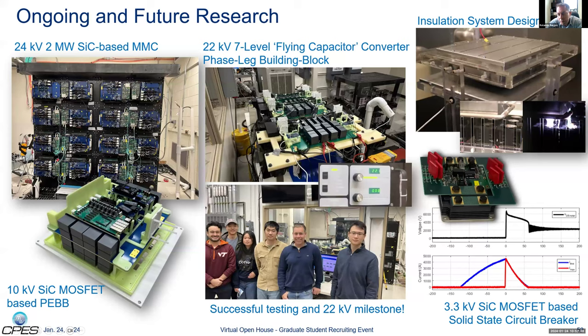That has allowed me, and CPES in general, to go more deeply into insulation system design. We've learned a lot. It's been a steep learning curve, but I'm very pleased with the work that's been conducted. We've been able to successfully test much higher voltages than we ever did in the past, and apply our circuit solutions, like the solid state circuit breakers you see here, demonstrating current interruption capability for a medium voltage DC bus.